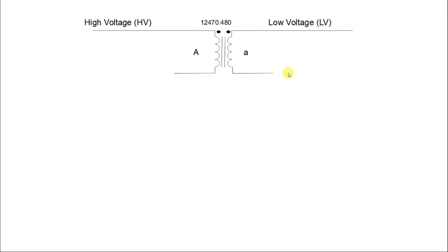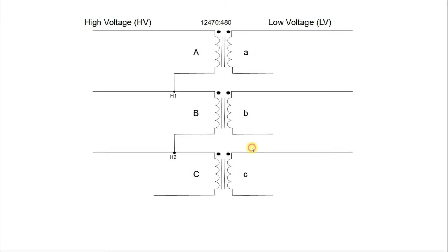Now, this side, I said in the video this was a delta to Y transformer - we're going to get into that a little more. I'll connect my primary up in delta: I take the non-polarized side of phase A and connect it to the polarized side of phase B. Then the non-polarized side of phase B connects to the polarized side of phase C. Finally, the non-polarized side of phase C connects to the polarized side of phase A. That puts me in a delta connection.